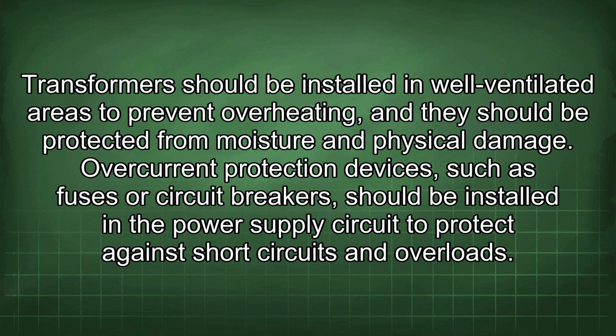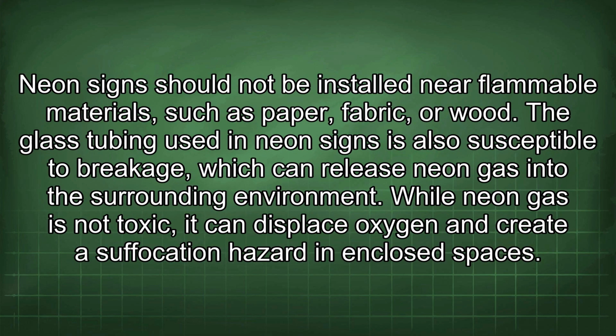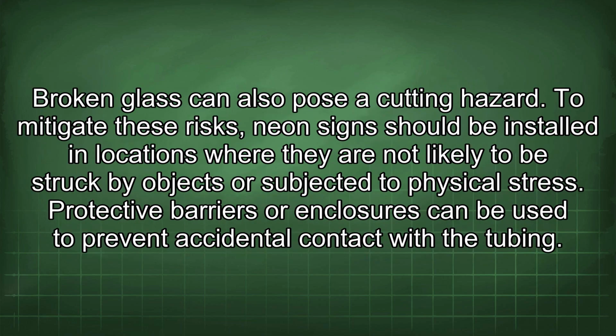Transformers should be installed in well-ventilated areas to prevent overheating, and they should be protected from moisture and physical damage. Overcurrent protection devices, such as fuses or circuit breakers, should be installed in the power supply circuit to protect against short circuits and overloads. Neon signs should not be installed near flammable materials, such as paper, fabric, or wood. The glass tubing used in neon signs is also susceptible to breakage, which can release neon gas into the surrounding environment. While neon gas is not toxic, it can displace oxygen and create a suffocation hazard in enclosed spaces. Broken glass can also pose a cutting hazard.